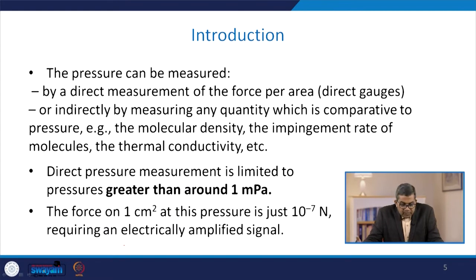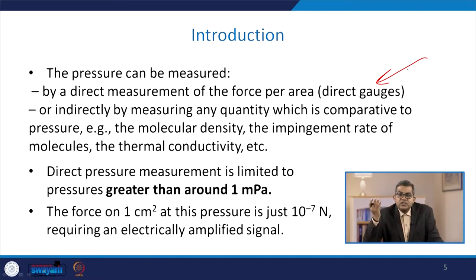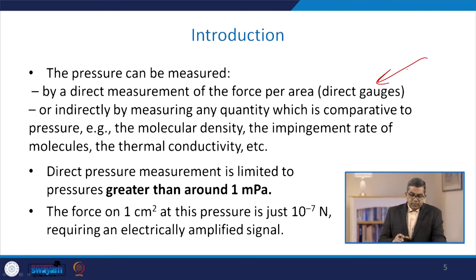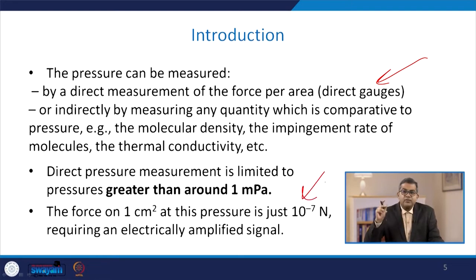Pressure can be measured either by direct measurement of force per area (a direct gauge) or indirectly by measuring any quantity comparative to pressure, such as molecular density, impingement rate of molecules, or thermal conductivity. Direct pressure measurement is limited to pressures greater than around 1 milliPascal; the force on 1 square centimetre at this pressure is just 10⁻⁷ Newton, requiring an electrically amplified signal.